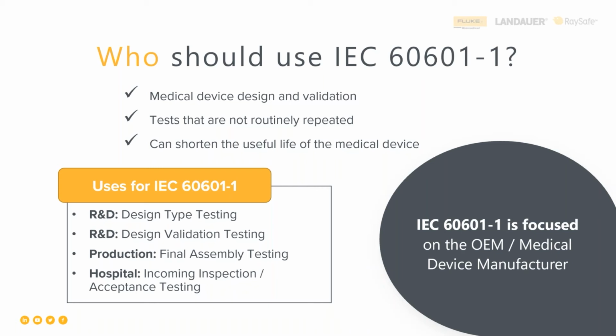So some countries adopted the IEC 60601-1, but then didn't provide any other standard for use by the hospitals. And this happened in many countries in Western Europe. And so now in Asia Pacific, we see sometimes that happening as well. Remember that this standard has a couple of tests that would tend to shorten the useful life of the medical device. They're perfectly appropriate for design validation testing, and they're perfectly appropriate for final assembly testing, but we don't want to shorten the useful life of the medical device in the hospital, or clinic, or wherever we find it. So for that reason, there's another standard that gets used.